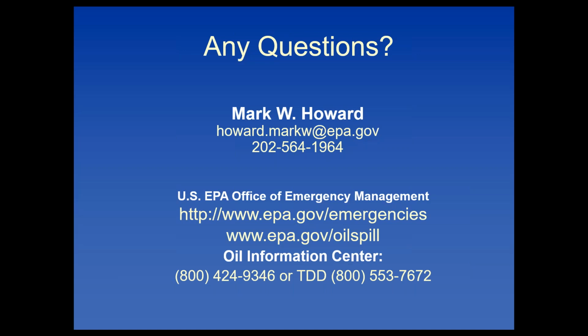One person mentioned that they had utilized the EPA website SPCC applicability tool to see if the fuel tank farm for a large municipal airport was subject to the rule, but the tool made it seem like since the airport was transportation related, it was not subject to the rule. Yes, that's an incorrect analysis. As I mentioned earlier, it's not whether the facility is involved in transportation. Transportation in the context of applicability means the transportation of oil. So if that airport stores oil, it is regulated, absolutely regulated, if it's over the threshold.